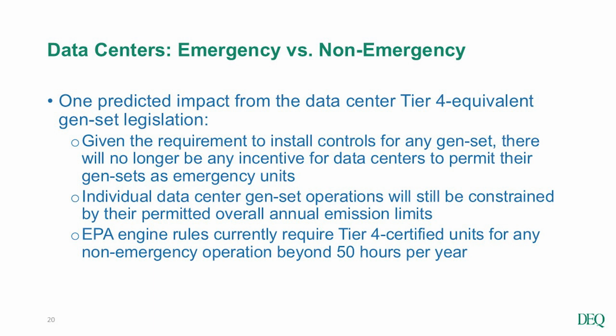And so we've gotten some questions about, well, does that mean they're going to be able to operate those units a lot more, since they now will be non-emergency versus the restricted operations of an emergency unit? In theory, yes, but as far as we've been able to tell, probably the answer is really no, because they will still have to comply with their annual emission limits and those related annual fuel limits that we permit them at. Most of them are so large, 200 units, 300 units, and those gensets themselves are so large that even with the controls, they will have very limited hours of operation during a year to stay under their annual emission limits. Then also, EPA's engine rules do require Tier 4 certified units in order to operate beyond 50 hours per year for non-emergency use. So they would also still need to meet that number.